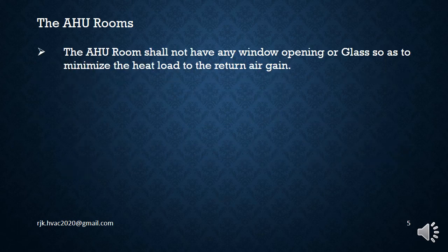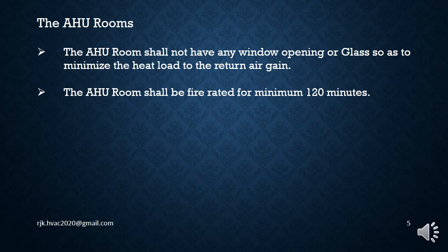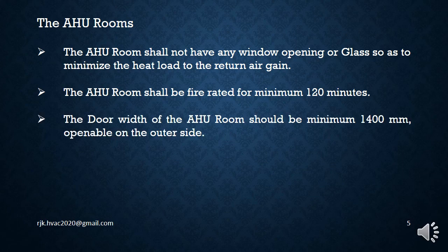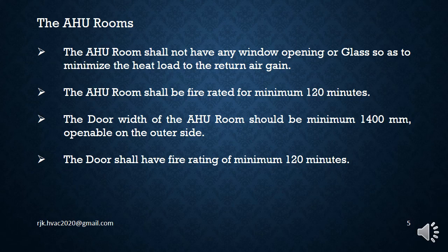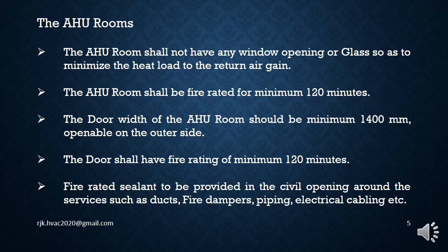The AHU room shall not have any window opening or glass, so as to minimize the heat load to the return air gain. The AHU room shall be fire rated for minimum 120 minutes. The door width of the AHU room should be minimum 1400 mm, openable on the outer side. The door shall have fire rating of minimum 120 minutes. Fire rated sealants to be provided in the civil opening around the services such as ducts, fire dampers, piping, electrical cabling, etc.